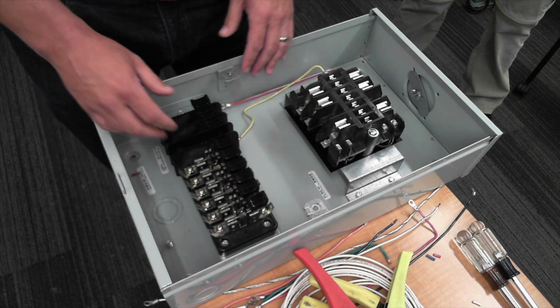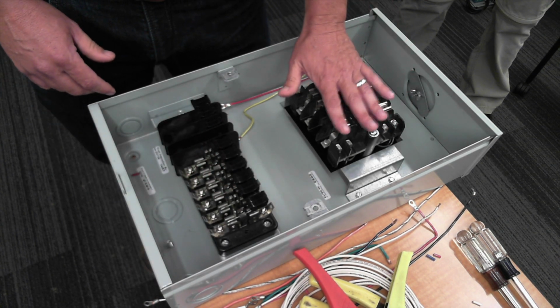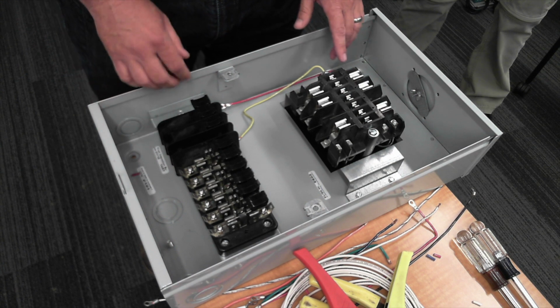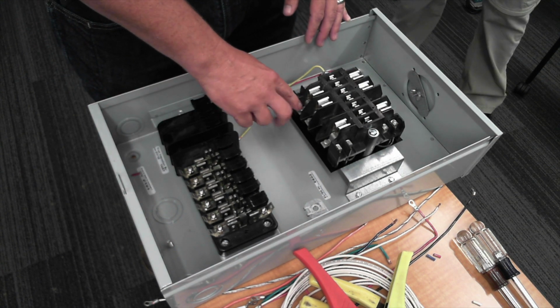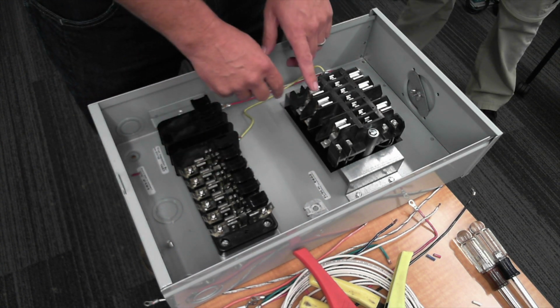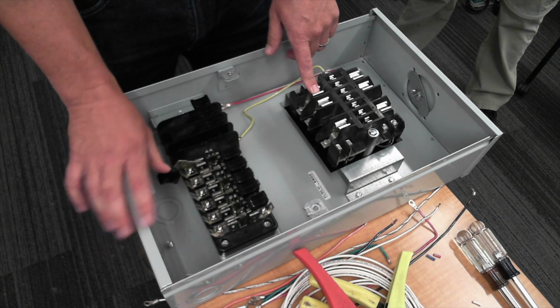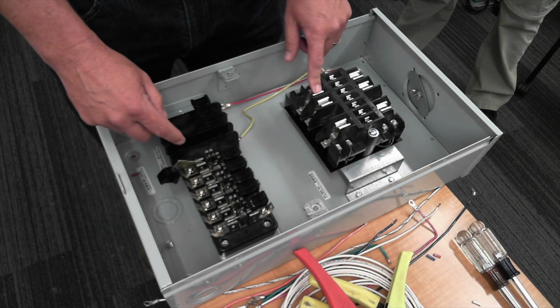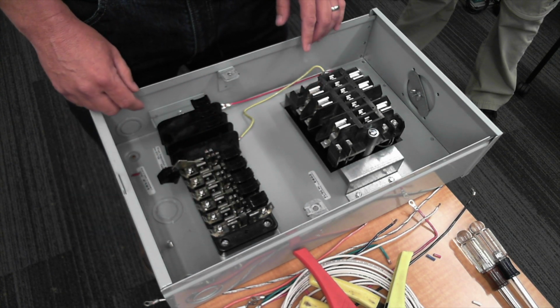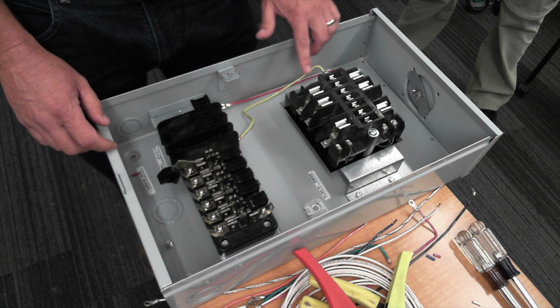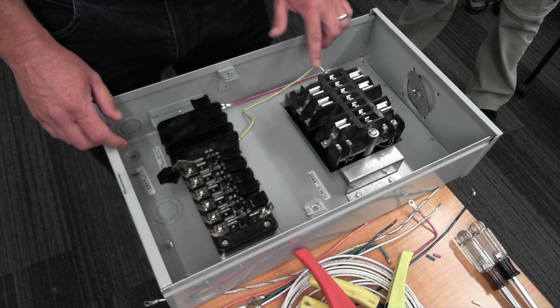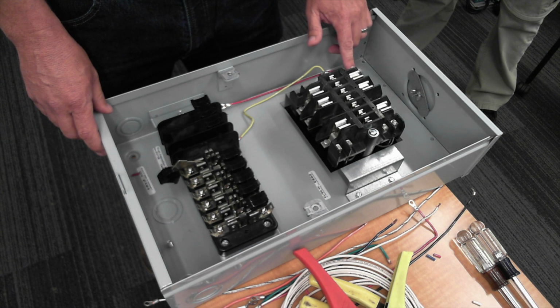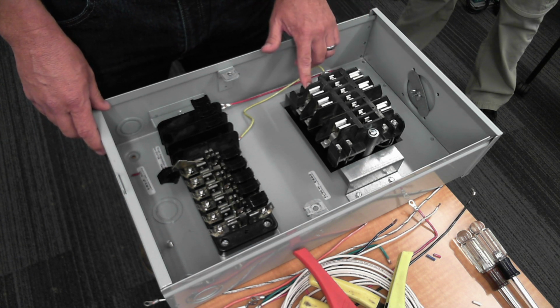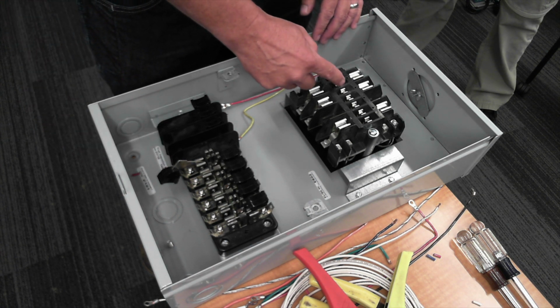Now that we've looked at the test switch, before we start wiring, we'll look at the top side of the meter base. Right here we'll start at the bottom - returns. As we said before, your returns come all the way open, A to A. Then over here on this side, if you can see where my finger is, this is where your voltages are going to go - A, B, C voltage, here's your little stabs.